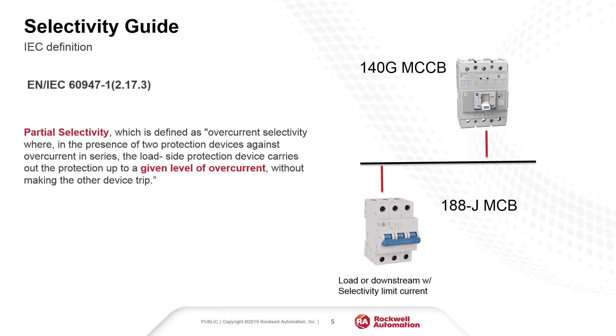What happens when Total Selectivity is not an option? In that case, we look at Partial Selectivity, which is defined per IEC 60947-1 as Overcurrent Selectivity where, in the presence of two protection devices against overcurrent in series, the load side protection device carries out the protection up to a given level of overcurrent without making the upstream device trip.